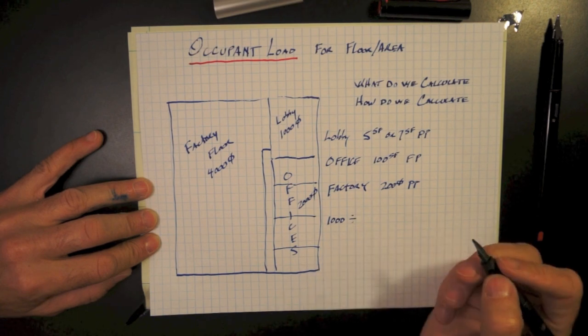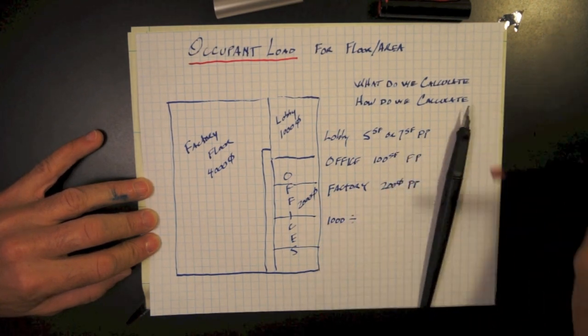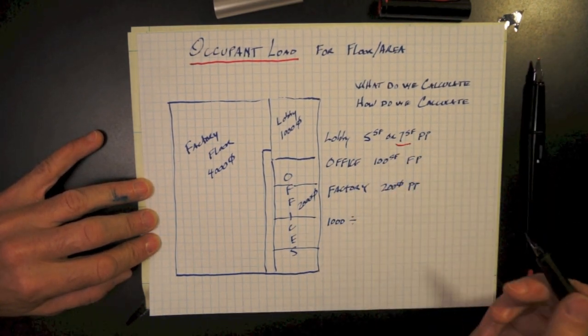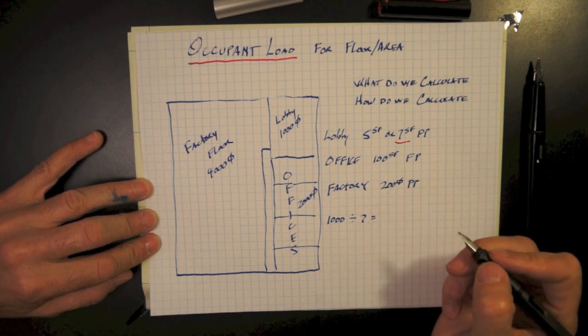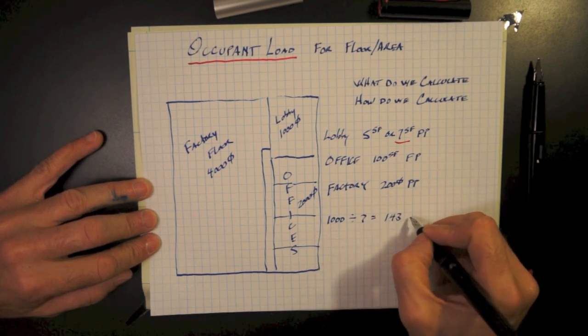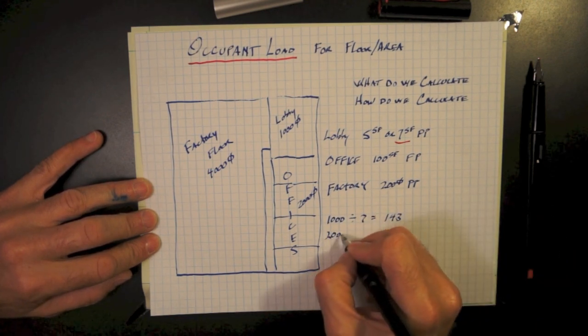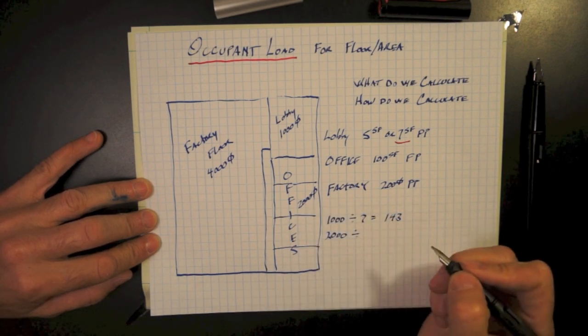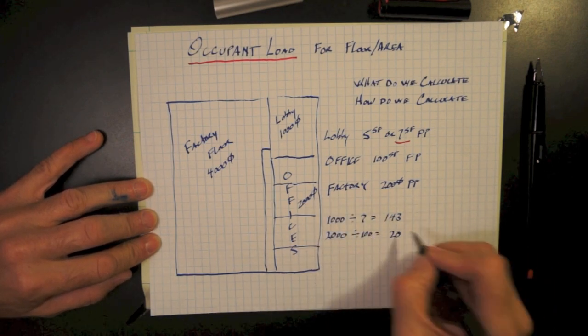So let's take the lobby at 1,000 square feet, divide that by 7. That equals 143 people in that lobby space that it could hold. 2,000 square feet for the offices, divided by 100, that gives us 20 people.